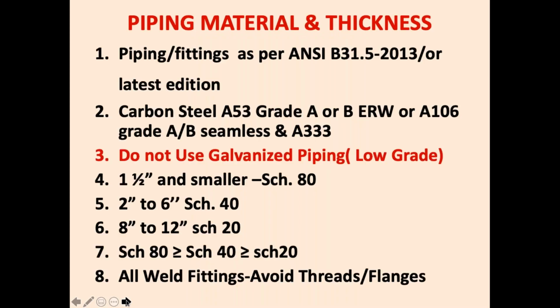The next slide shows what piping material and thicknesses to be used. Use piping and fittings as per ANSI B31.5 2013 or latest edition. Carbon steel A53 grade A or B ERW pipes or A106 grade B seamless pipes, or for low temperature, A333 pipes.